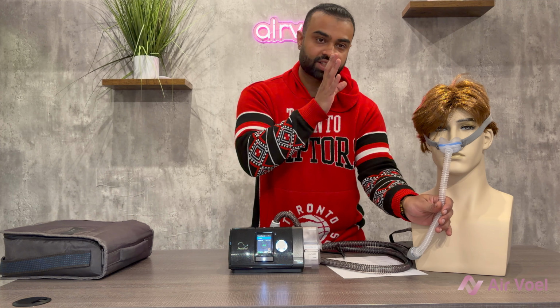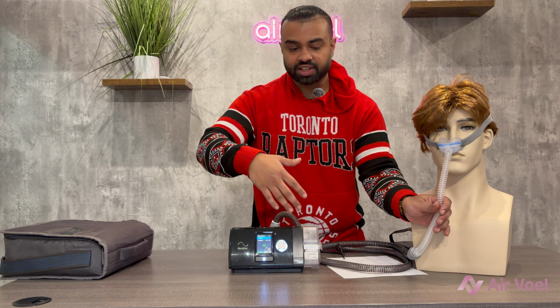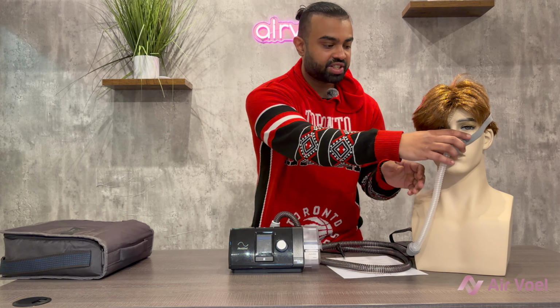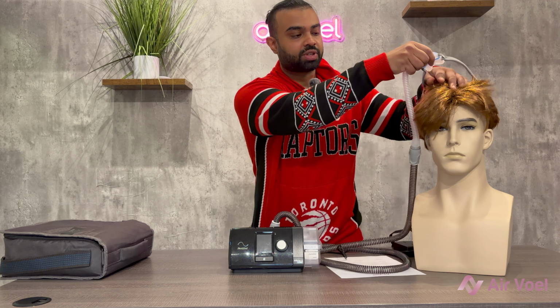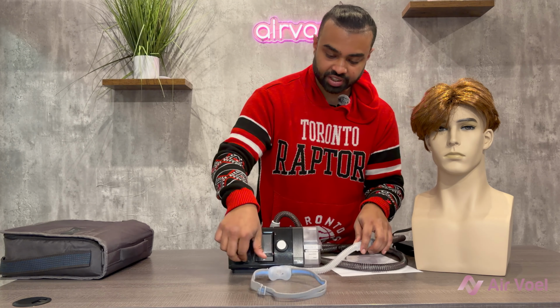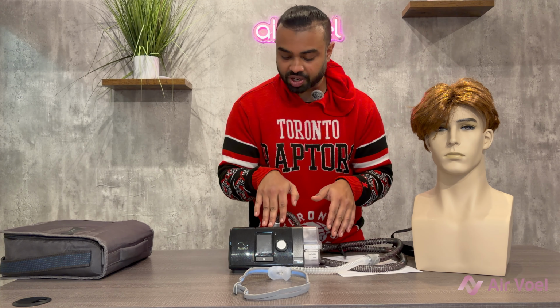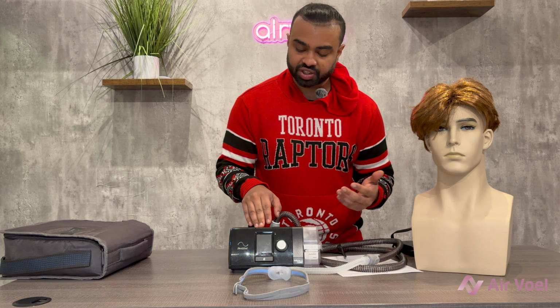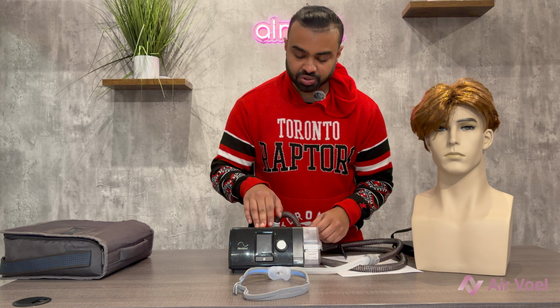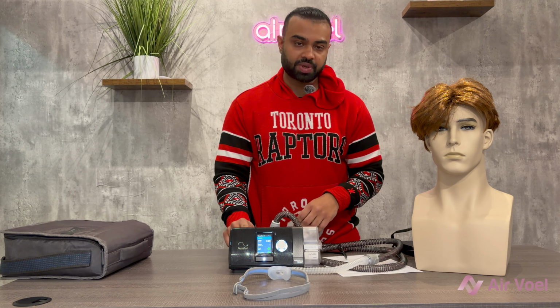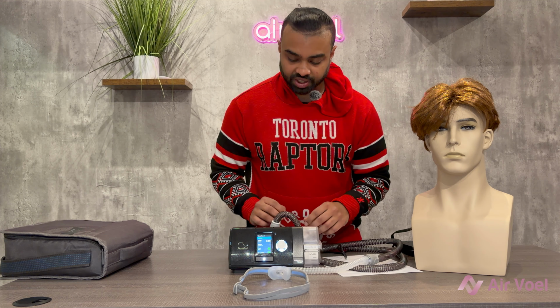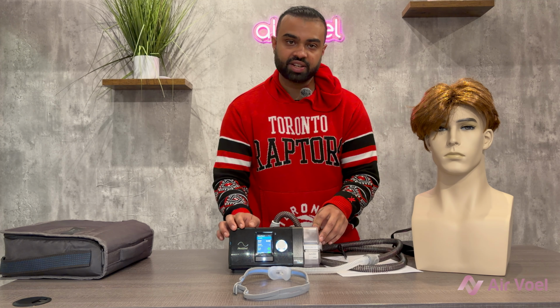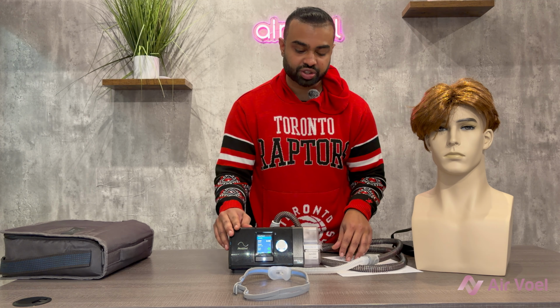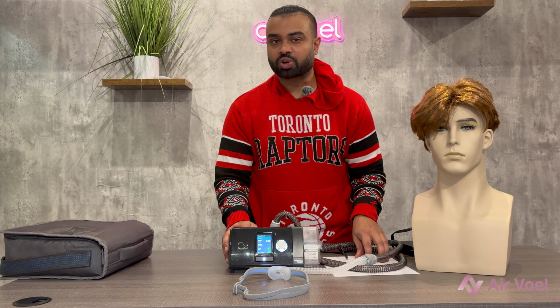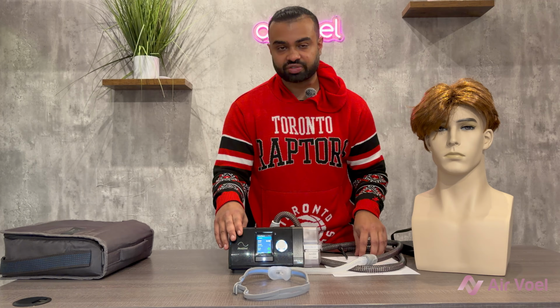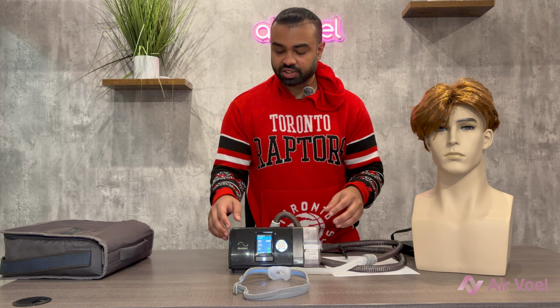Okay? Now, when Sam is done therapy, waking up in the morning, or they just need to go to the washroom for any reason, they're going to simply just remove their mask, hopefully not toss their wig off. Once they remove the mask, if the Smart Start setting is on, the machine will turn off on its own. It can take up to 30 seconds to do so, or you can press the button for an immediate response to stop your therapy. Okay, you can then review your sleep report page to make sure that you had low events and adequate usage, and make note of anything that seemed problematic over there to bring up to your vendor or your physician. And then you're basically done therapy.